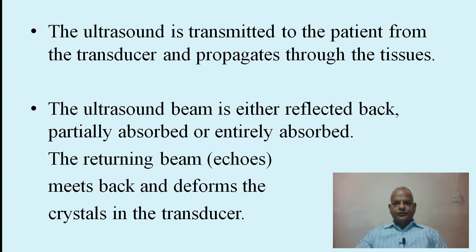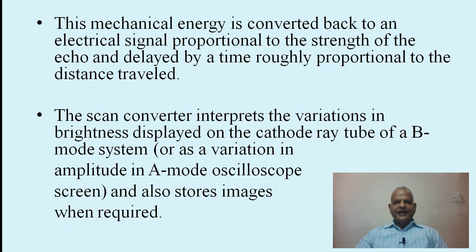The ultrasound beam, when it strikes live structures, is either reflected back, partially absorbed, or entirely absorbed. The returning beam or echoes meet back and deform the crystals in the transducer. This mechanical energy is converted back to an electrical signal proportional to the strength of the echo and delayed by a time roughly proportional to the distance traveled.